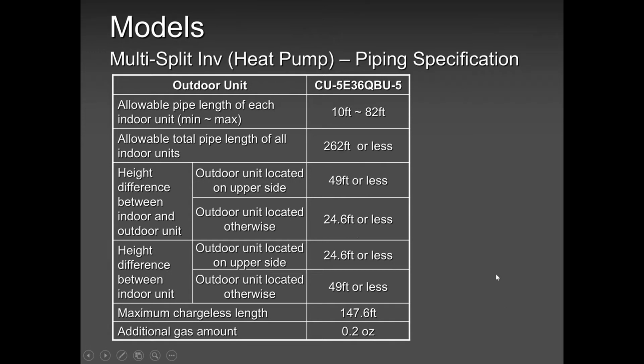Okay, guys? So remember, this unit is charged only for 147.6 feet. The moment you cross 147, you need to add refrigerant. And please, if I were you, I would always look into my installation manual to get the latest info. Okay? Installation manual will give you the latest info, how much additional refrigerant is required once you cross the maximum pipe length, or once you cross the length that the unit was charged for.